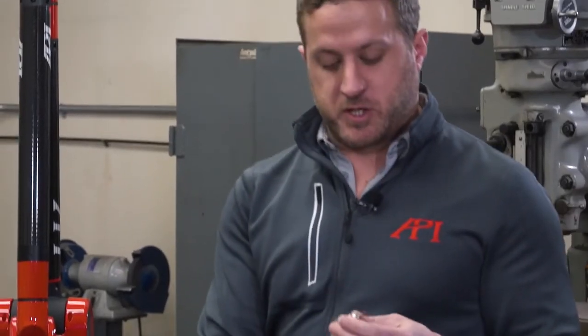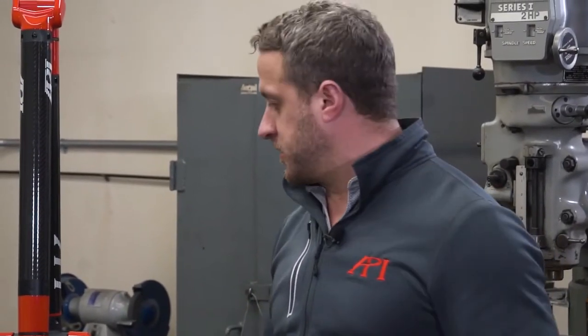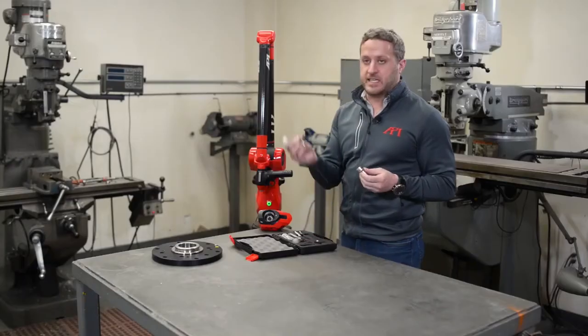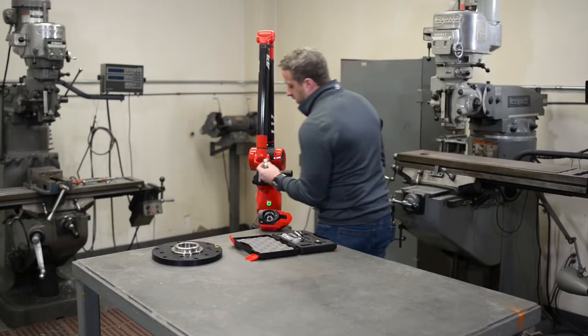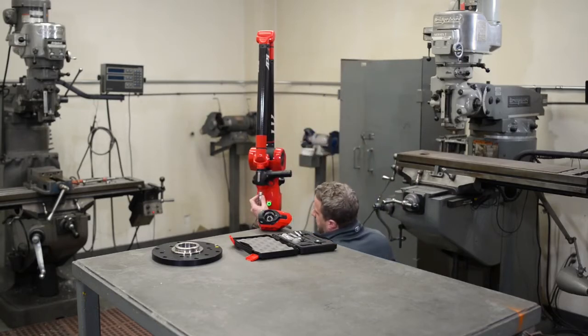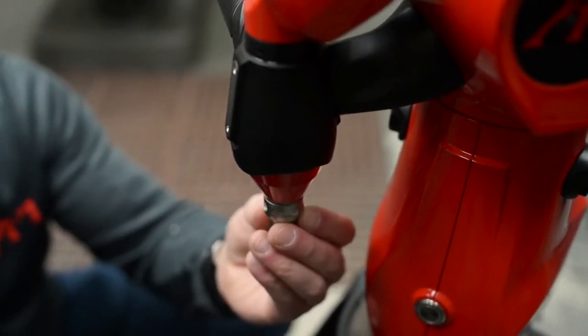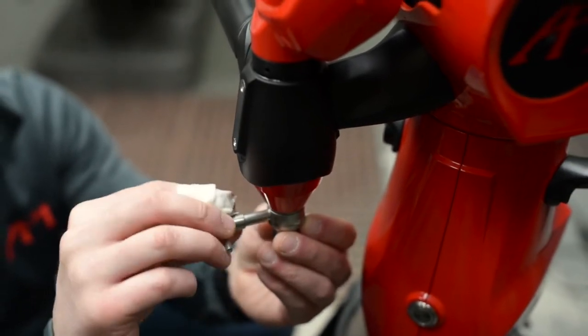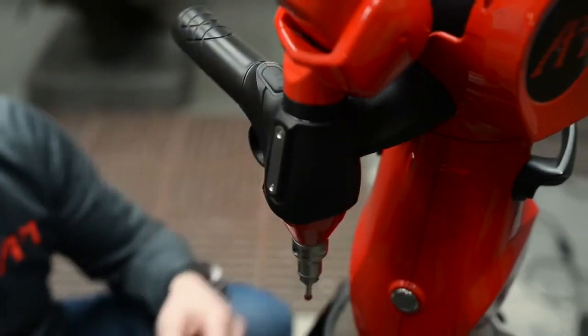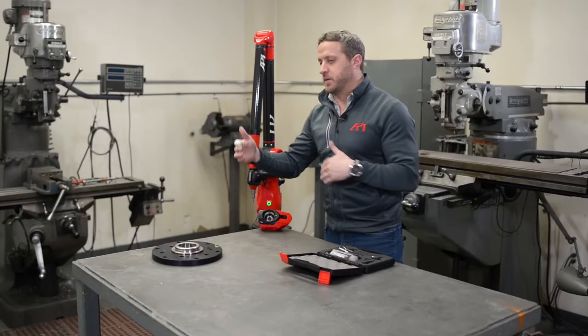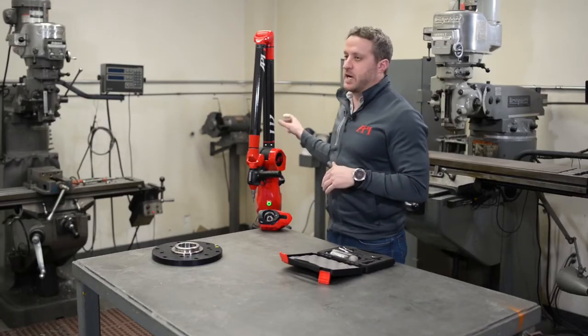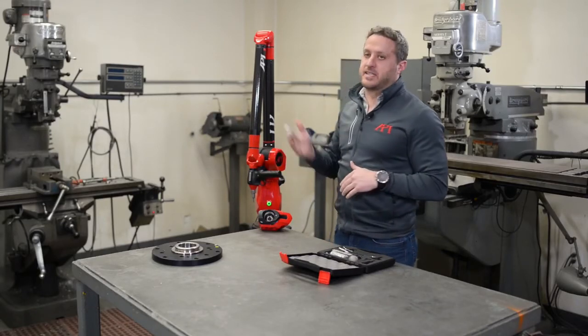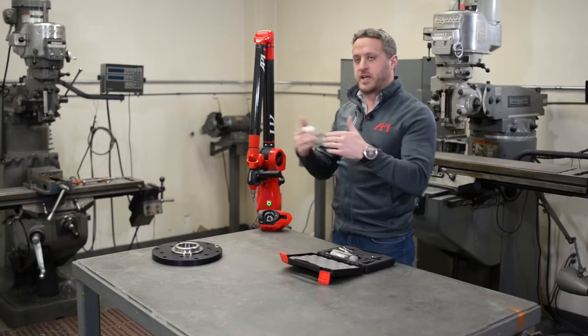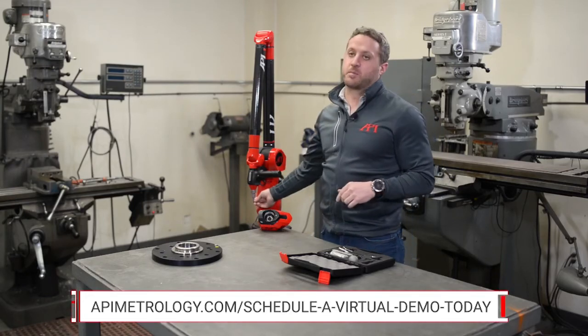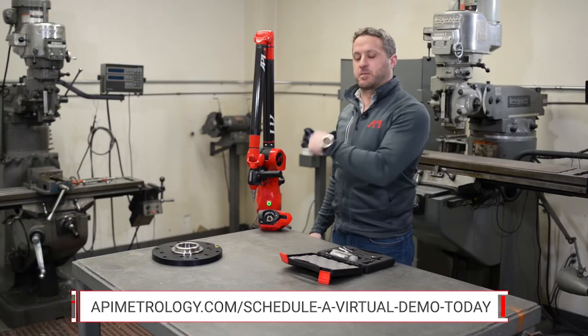So now I'm going to demonstrate installing the probe onto the arm and then going through a calibration process. There is a key inside the toolkit. What we're going to do is index the probe tip onto the arm, and then use the key to lock it on. Next, I'm going to grab my computer and we're going to go through how to connect to the arm, check diagnostics, see if the arm is ready to be run, and then we're going to go through the probe management and calibrate that probe.